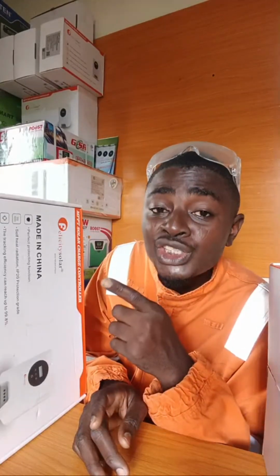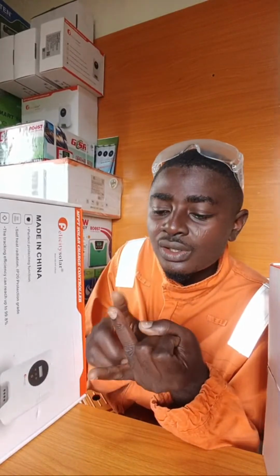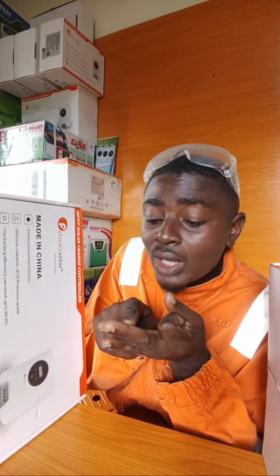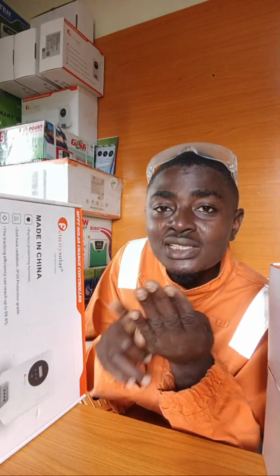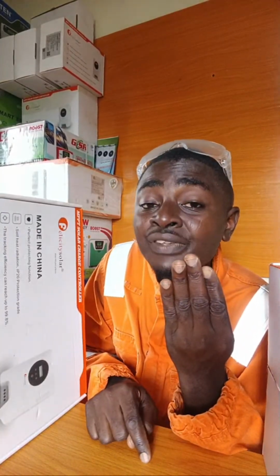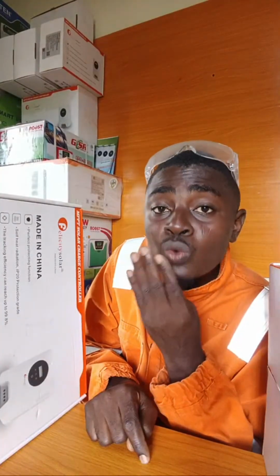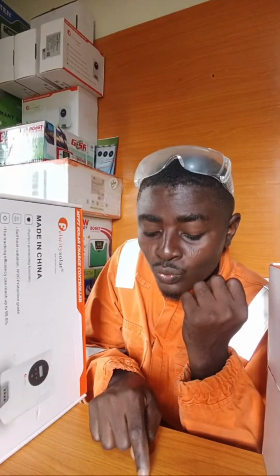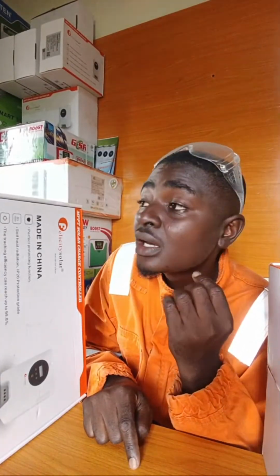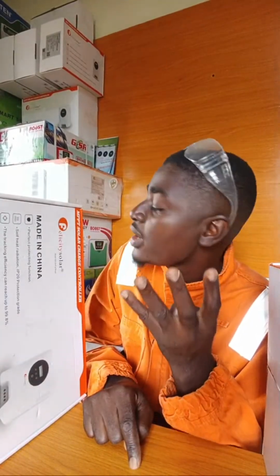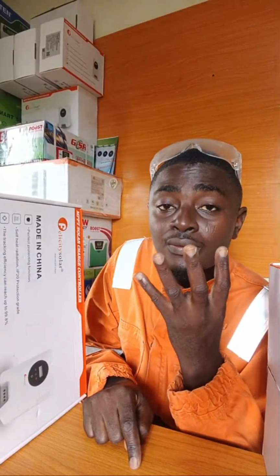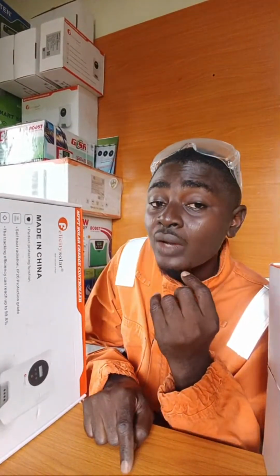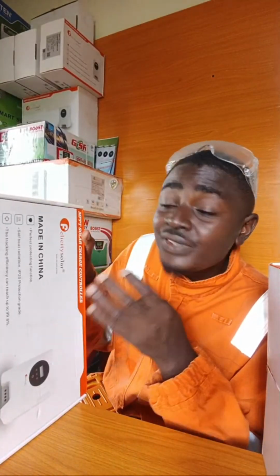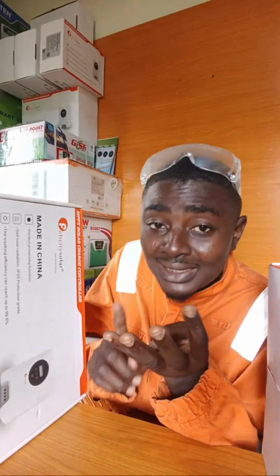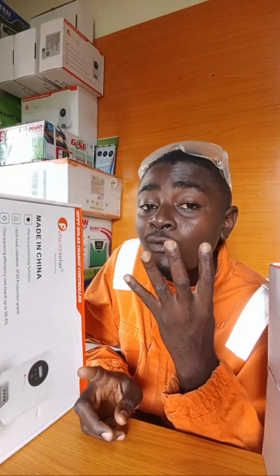Now how do you connect it? The VDC of each panel is 40. So 40, 80, 120, 160 — if I connect 4 panels as one string, I get 160 VDC. That's 40 times 4 equals 160. So if I connect 4 as one, I get 160 VDC — that's 4 solar panels of 40 VDC each connected together as one string.